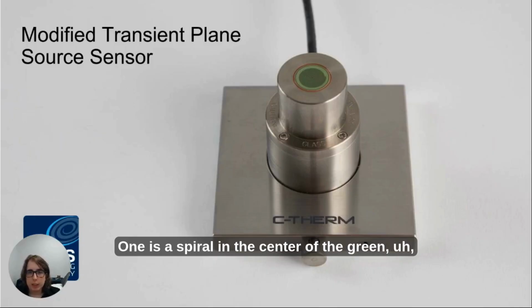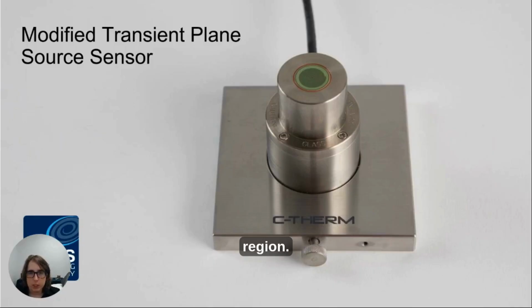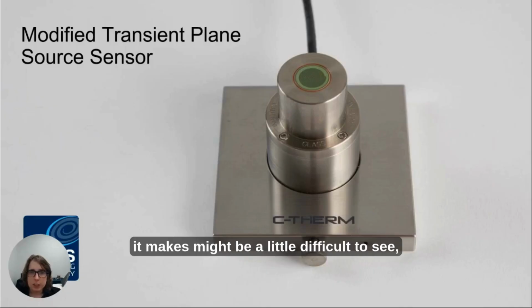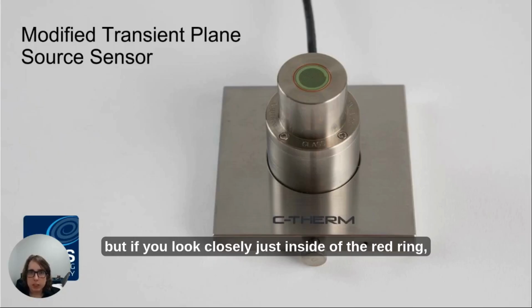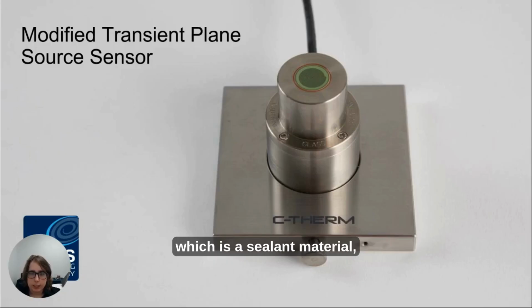So you can see that the sensor has two parts. One is a spiral in the center of the green region. And then on the outer edge, it might be a little difficult to see, but if you look closely, just inside of the red ring, which is a sealant material, you'll see another dark trace. And that's the guard heater.